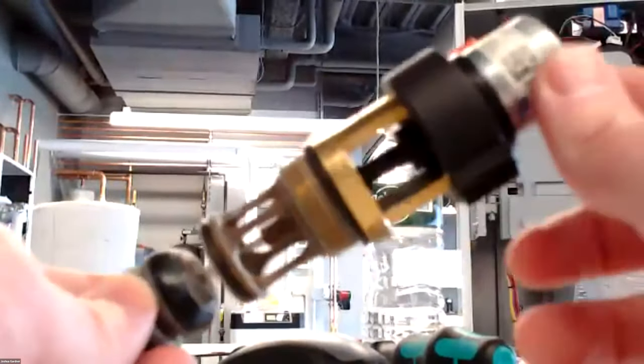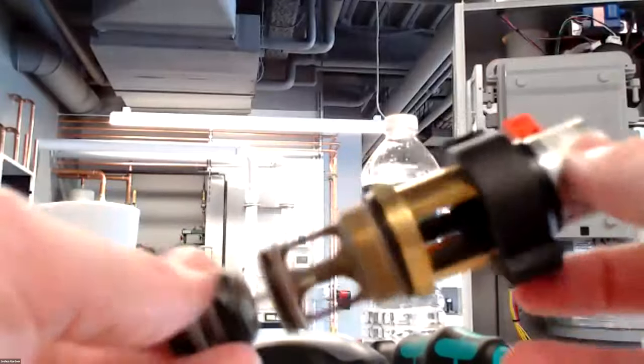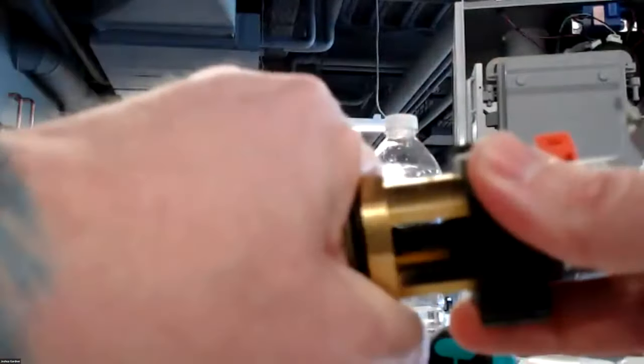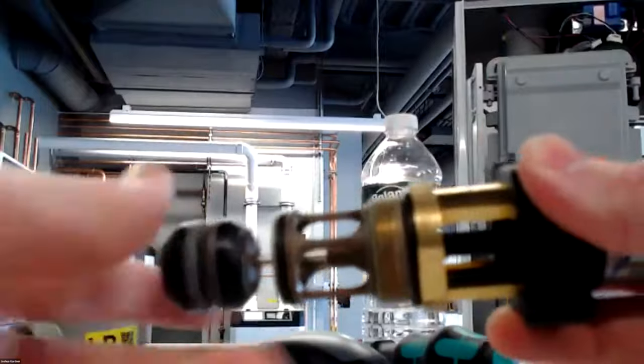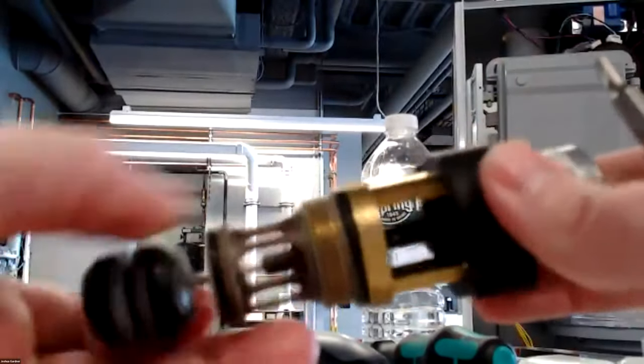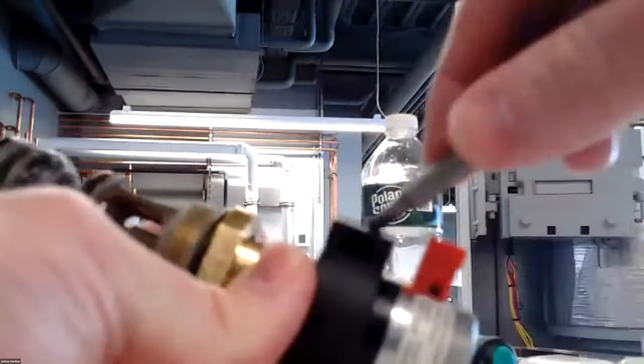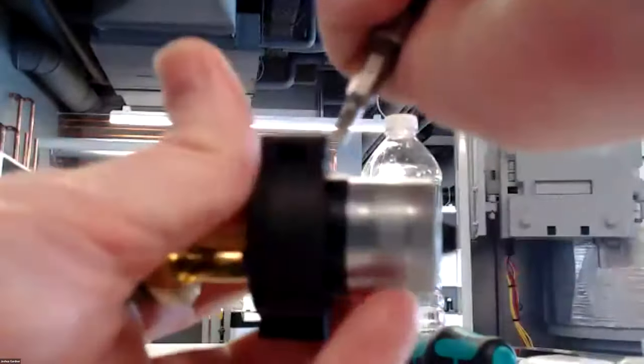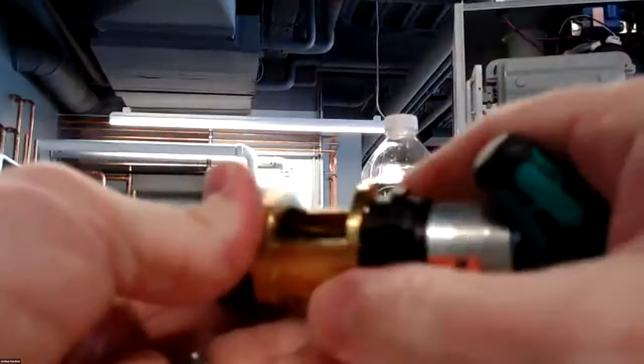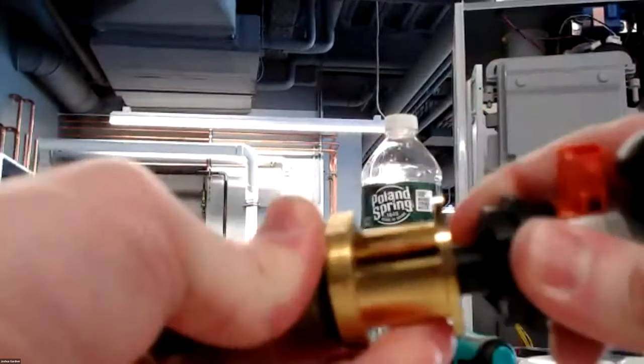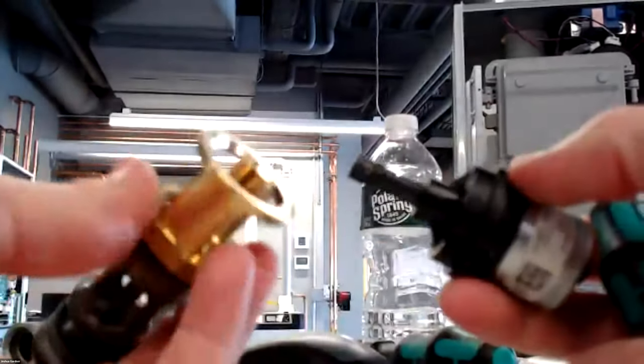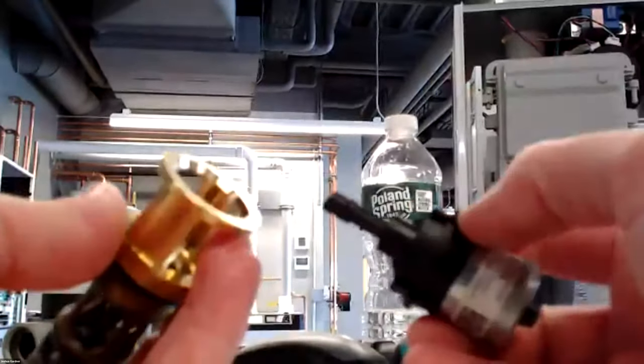This is what it looks like completely removed. You have your electrical connections right here. You'll have a clip that holds this, and this will be threaded in. And this will all be a wet connection from this point on, and this is all dry, exposed. So to remove your solenoid, you'll just take a screwdriver, pop it in here, pop this in here, pop that clip, and then you'll be able to remove the solenoid valve from the unit. And that's a dry connection, so it's easy to swap out.